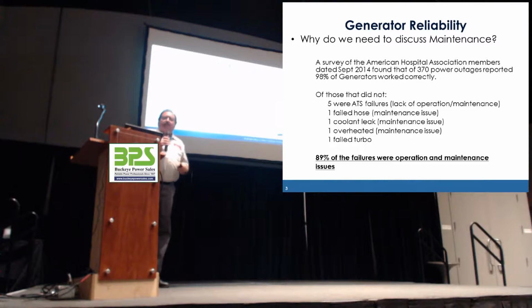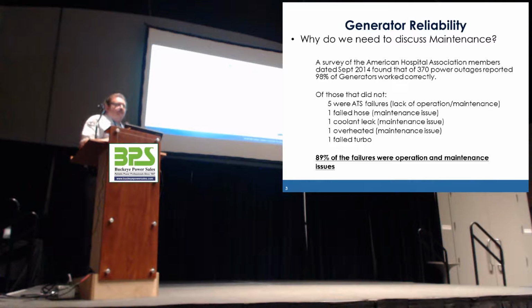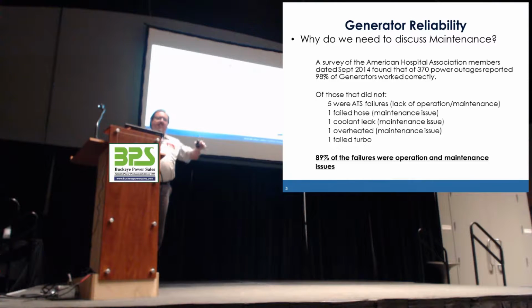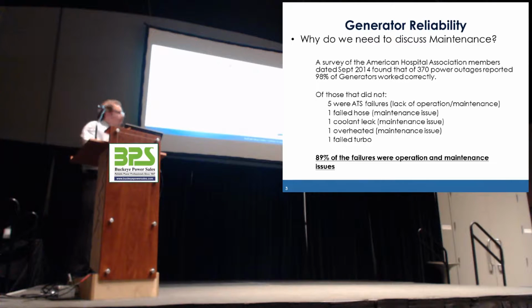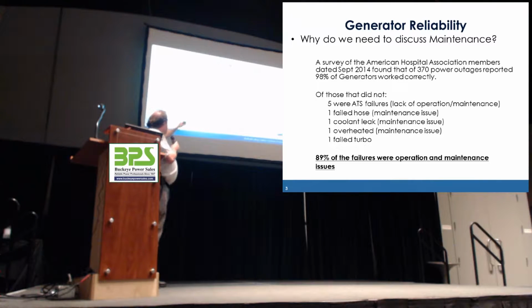We always talk about the generator, and everybody always wants to test the generator and run the generator, but when I come into the facility and say, okay, now we have to put that generator onto your site and transfer the transfer switch, it's going to take an act of Congress to get that done. Well, if you don't operate a piece of equipment and it sits and it sits, it's not probably going to operate when you need it to. So that's why we want to look at these, because of these failures, 89% of them were due to lack of maintenance.